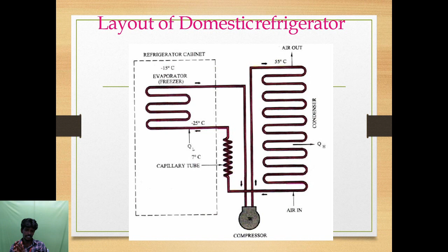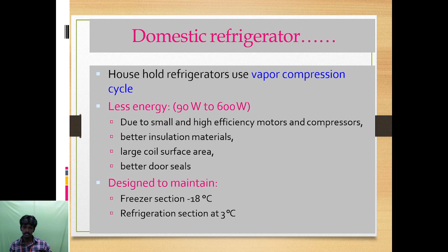Domestic household refrigerators use the vapor compression cycle with less energy, 90 watts to 600 watts, due to a small, high efficiency motor and compressor, better insulation material, large surface area and better door seals. If the door leaks, if it is unsealed, we have more power consumption. The seal is a very necessary thing. It is properly designed to maintain the freezer section at minus 18 degrees Celsius and the refrigerator section at 3 degrees Celsius.